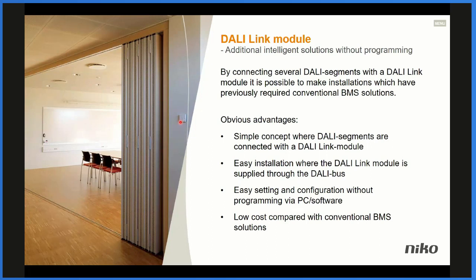This solution can be used if you, for instance, have a folding door solution. That means we have to communicate with one or more masters. This is an easy way of doing it. The link module actually supplies the communication through the DALI bus. It is done without any programming or any software from the PC. It's actually done by the app. And this solution is mostly low cost compared to a conventional BMS system. It could be a KNX system or another BMS system.